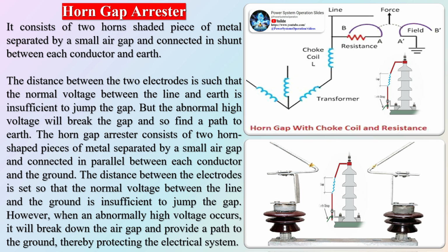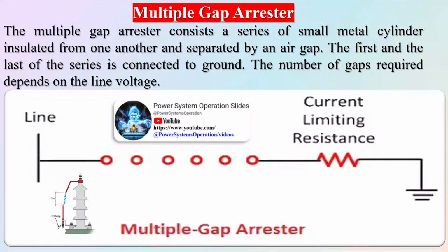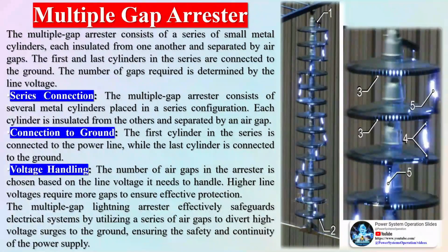When a traveling wave reaches the arrestor, it sparks over at a certain prefixed voltage as shown in the figure below. The arrestor provides a conducting path of relatively low impedance to the waves between the line and the ground. The surge impedance of the line restricts the amplitude of current flowing to ground. The lightning arrestor provides a path of low impedance only when the traveling surge reaches the surge diverter, neither before it nor after it. The insulation of the equipment can be protected if the shape of the voltage and current at the diverter terminal is similar to the shape shown.